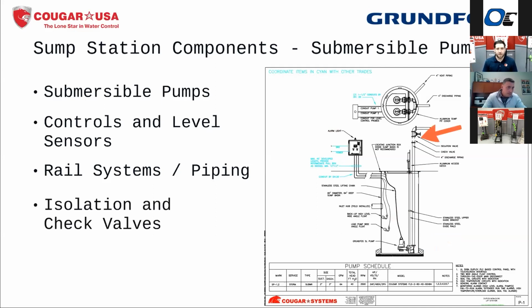Isolation valves and check valves, we're showing them coming straight out of the top here of our pit. And this is going to be our basin here with our cover. And then you can see from the top view here, this is showing the piping coming straight out of the top there, and then having our isolation valves and check valves outside of the pit for easy access.